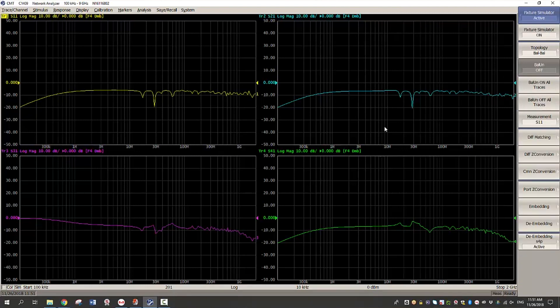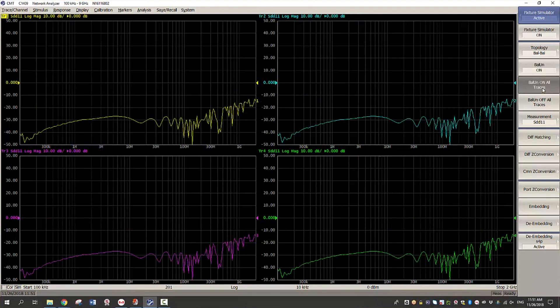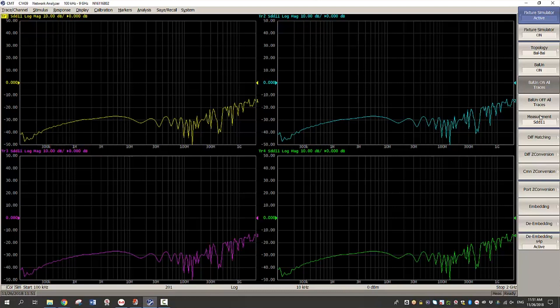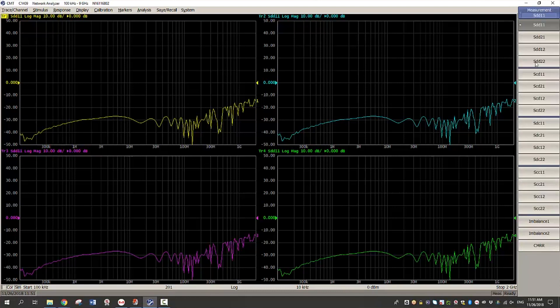Final step is to turn on balance measurements. So once you've turned on balance measurements by default all the traces would indicate return loss measurements at port one. So you'll want to change that to see return loss and insertion loss both forward and reverse.